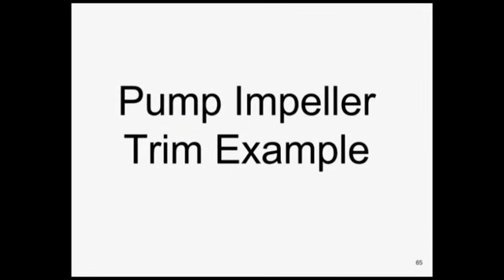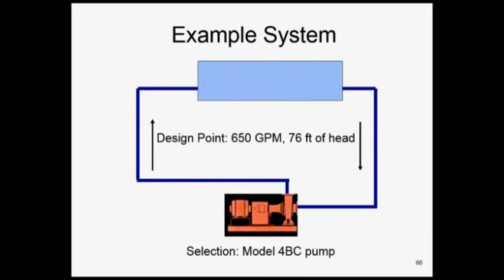So let's do a pump impeller trim example. I've got a pump here, it's a Model 4 BC, doesn't matter, but the pump has been specified and purchased and submitted to do 650 GPM at 76 feet of head. And that 76 feet of head by ASHRAE should be the critical circuit, remember? And if we say the design point was 650, you're telling me I need at full load 650 GPM. I don't need 800, I don't need 750, I need 650. That will satisfy this job. I don't need to pump any more than that because the more you pump, the more energy you're wasting, remember? And I need 650 GPM, and I've calculated the pump at 76 feet of head. So that's what we've got.